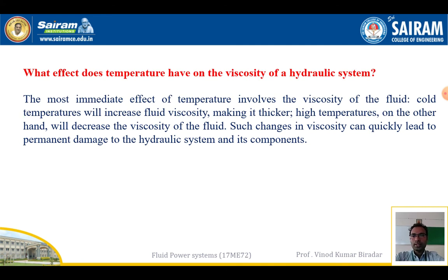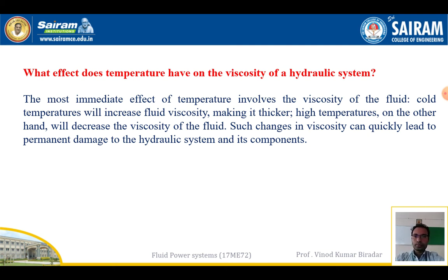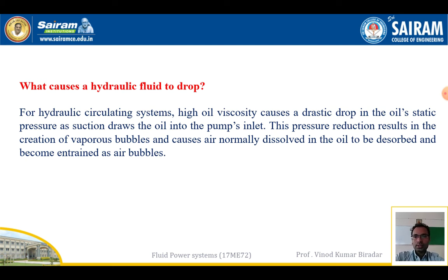The most immediate effect of temperature involves viscosity. Viscosity determines the nature of the fluid. Cold temperature increases the fluid viscosity, making it thicker, while high temperature decreases the viscosity. Such changes in viscosity can quickly lead to permanent damage to the hydraulic system and its components. High oil viscosity causes a drastic drop in static pressure as suction draws the oil into the pump inlet.